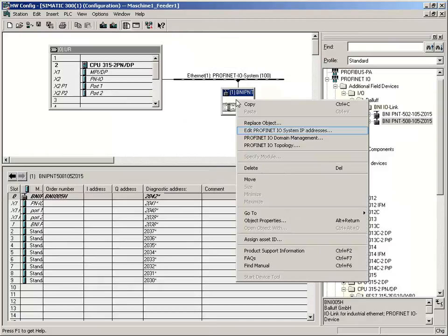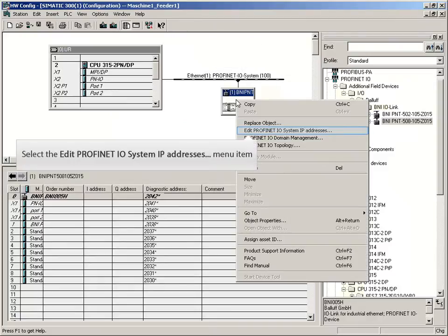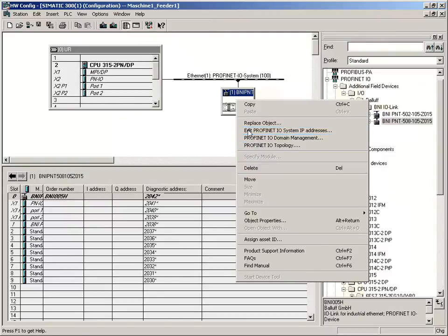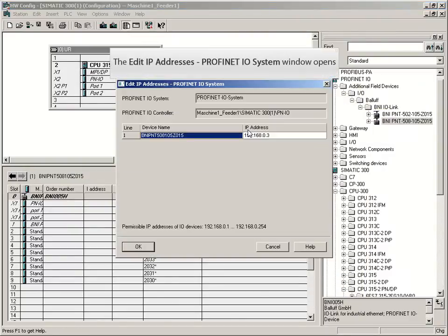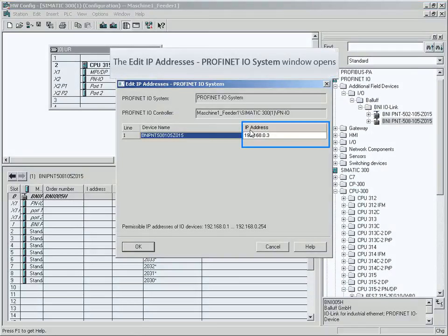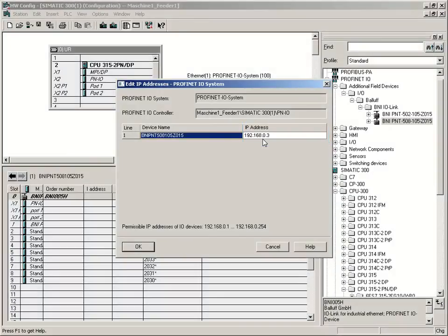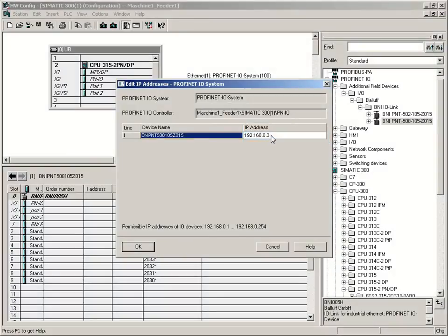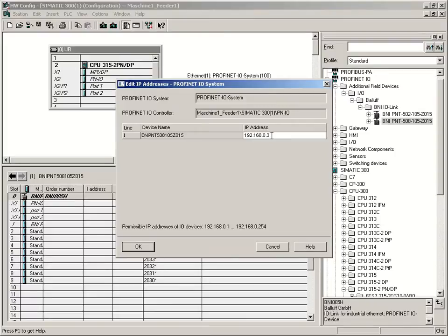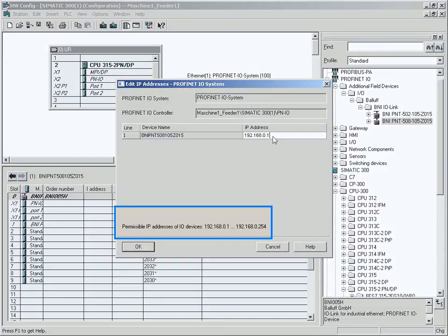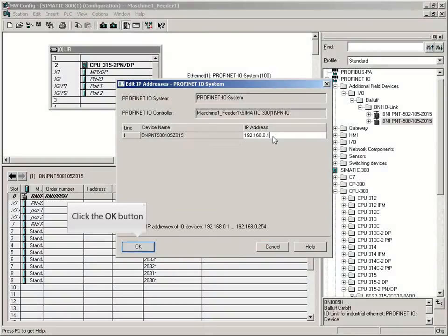To see the assigned IP address, just right-click on edit Profinet IO system addresses. The window displays the IP address 192.168.0.3. If you like, you can change it to 192.168.0.1. In the window at bottom you can see the possible IP addresses. Please confirm the assignments with the OK button.